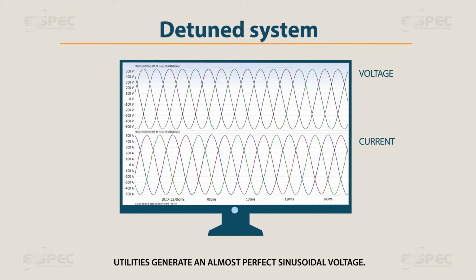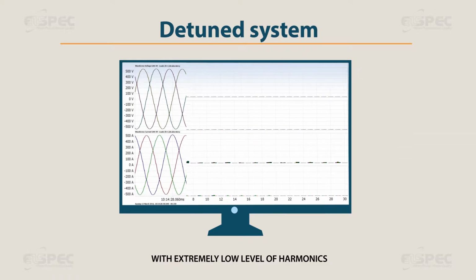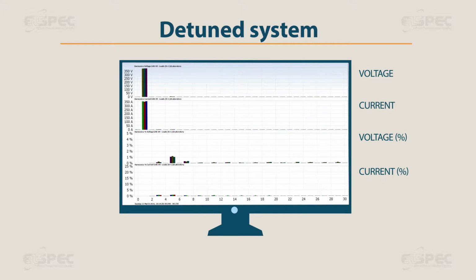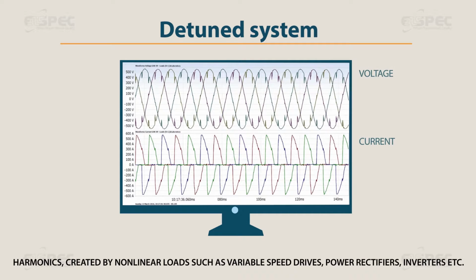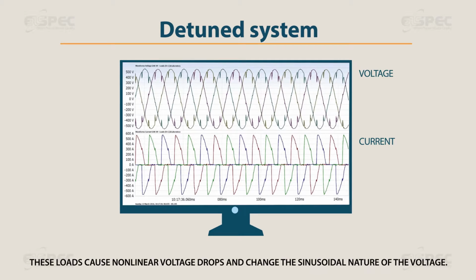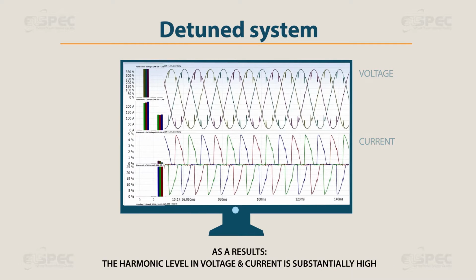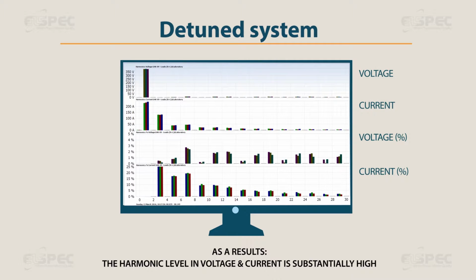Utilities generate an almost perfect sinusoidal voltage with an extremely low level of harmonics. Harmonics are created by nonlinear loads such as variable speed drives, power rectifiers, inverters, etc. These loads cause nonlinear voltage drops and change the sinusoidal nature of the voltage. As a result, the harmonic level in voltage and current is substantially high.